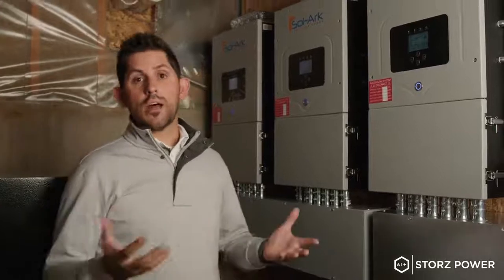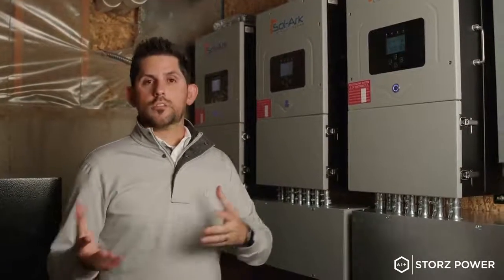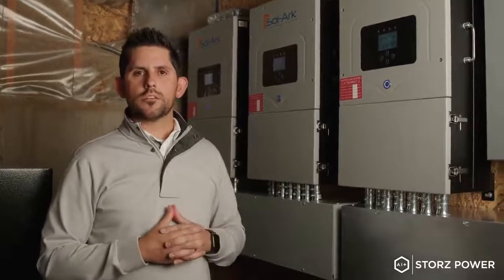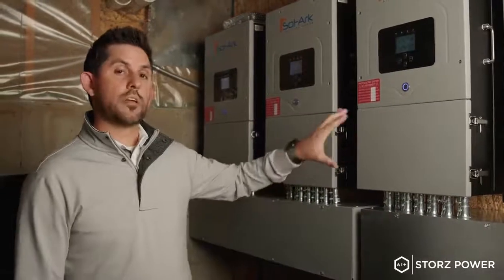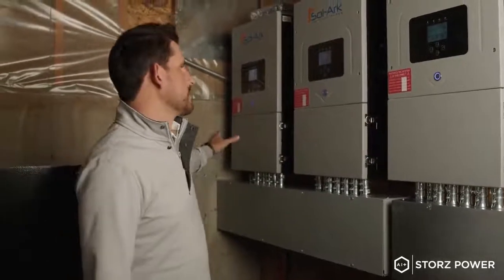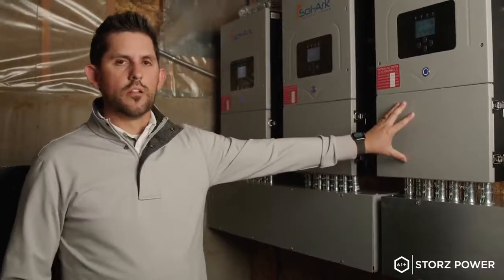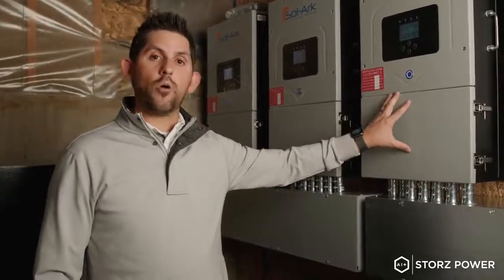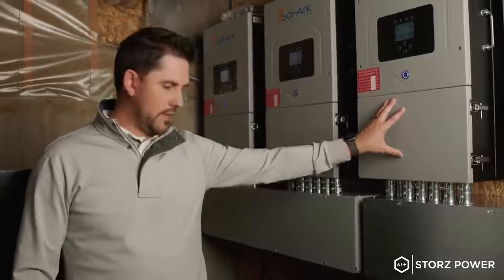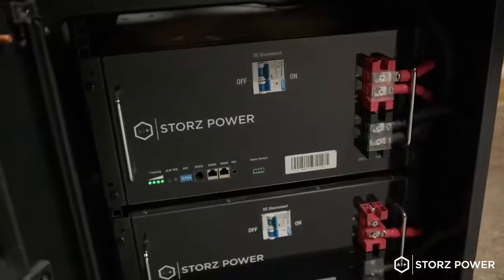There was liability in the fact that in these areas we have earthquakes and other torrential area challenges. Through that, what we were able to do is actually account for all independent home power systems. We included three of our AI Plus inverters that allowed us to provide enough power to the entire load. In addition to that, we have our battery banks down lower — we have 30 kilowatt hours of battery.